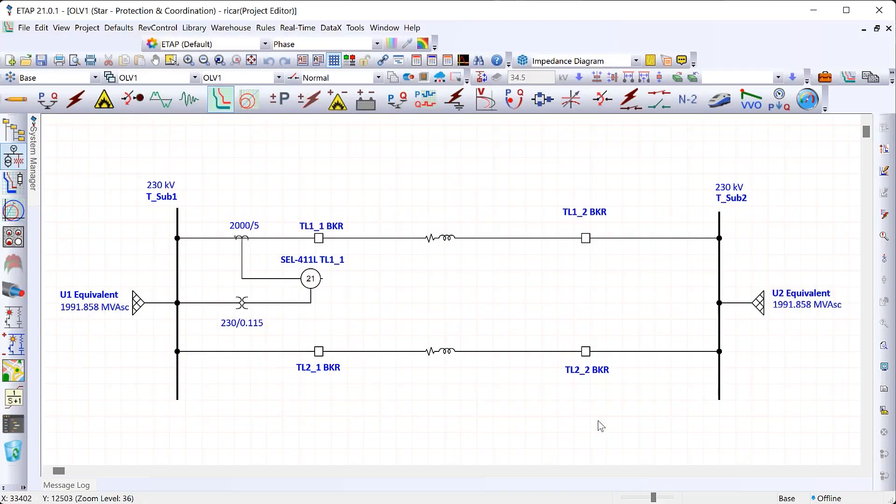To illustrate this, I've created an ETAP model of a 230 kV transmission system and we're going to be developing the ground distance protection for a 230 kV transmission line using an SEL 411L relay. Let's take a look at the example — what I have here is a 230 kV transmission system with parallel transmission lines between two substations.